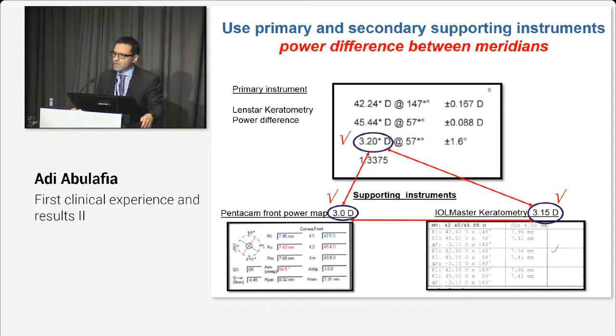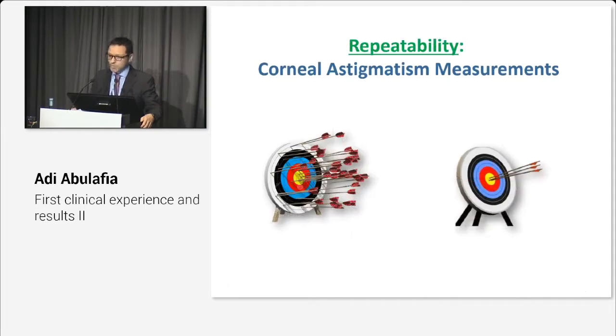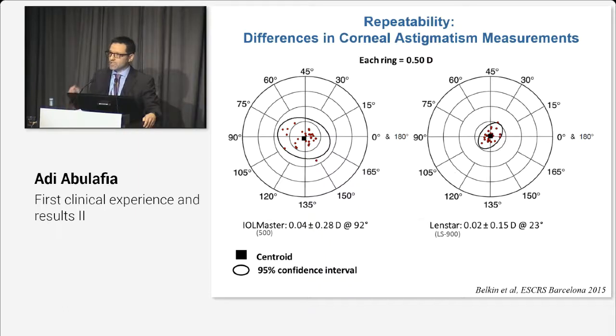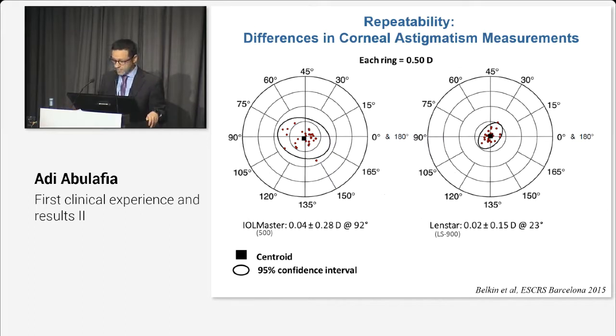For our primary device, we would like to use the best machine available — the most accurate one. Good repeatability is essential for high accuracy. Here are double-angle plots of the differences in the measured corneal astigmatism of healthy volunteers one week apart, taken either by the IOL Master 500 or the LENSTAR. In a perfect world, all these dots should be plotted against the zero mark since we are measuring the same eyes. However, the LENSTAR had a significantly lower variance as compared to the IOL Master.